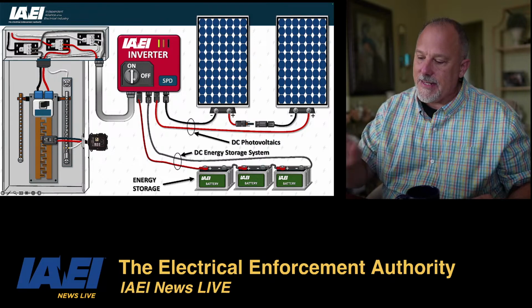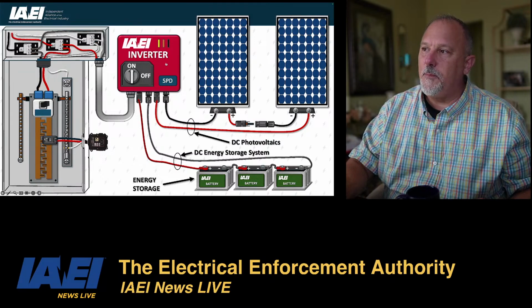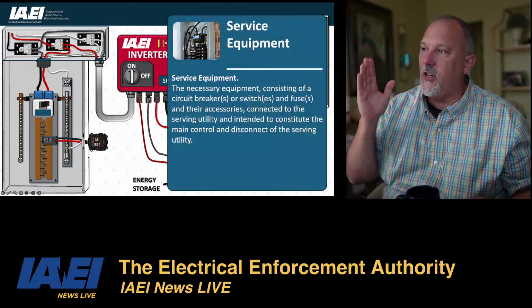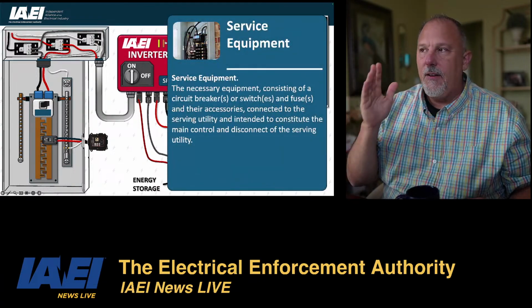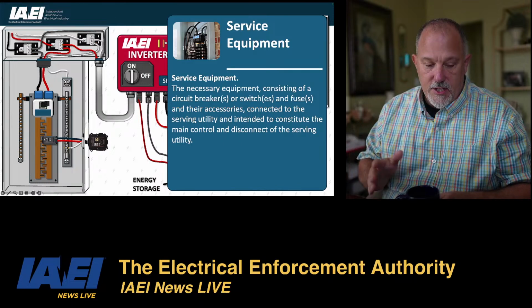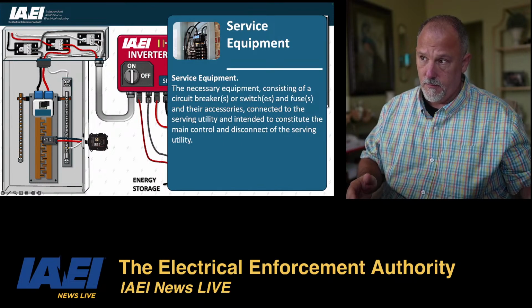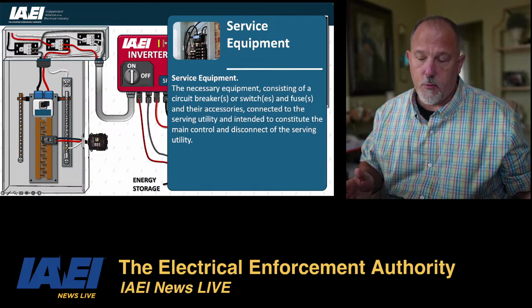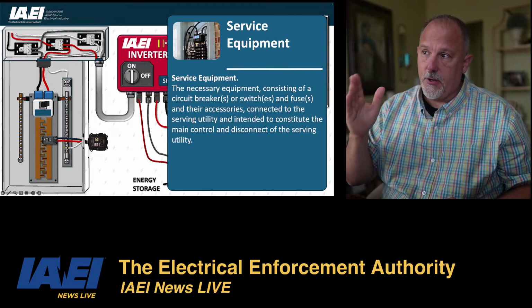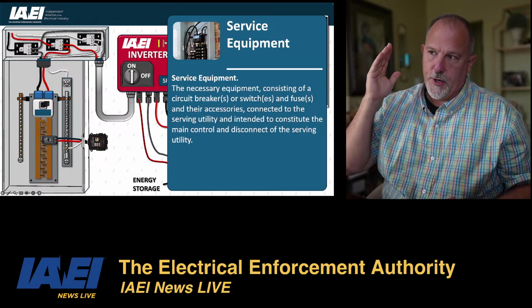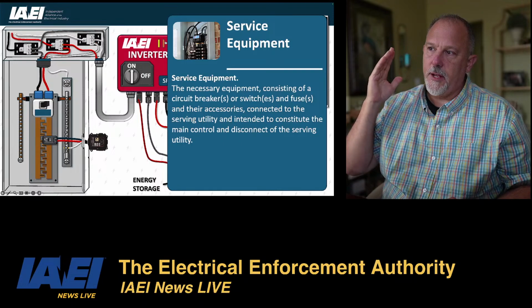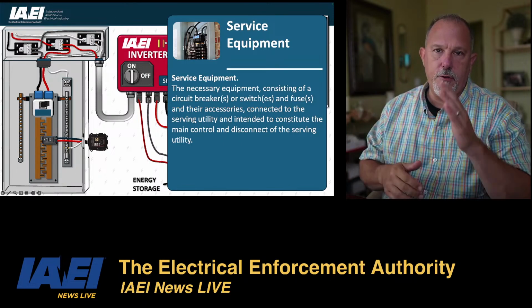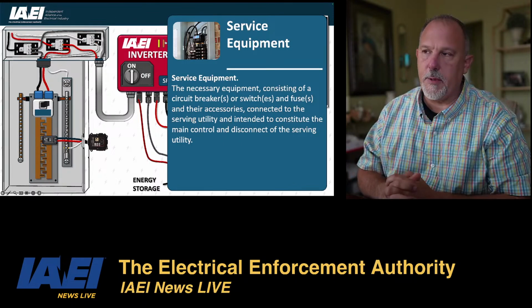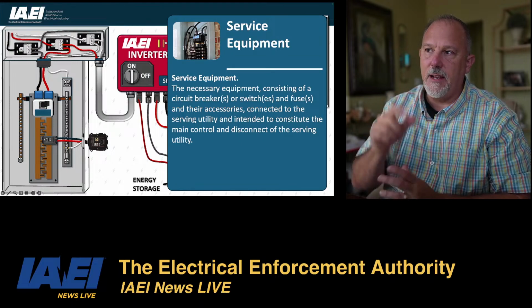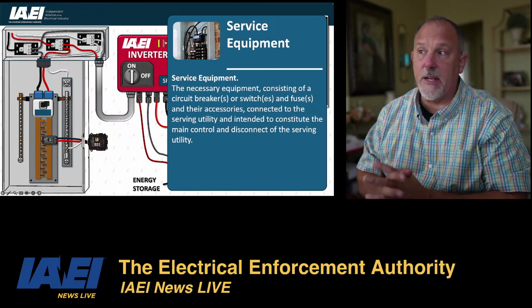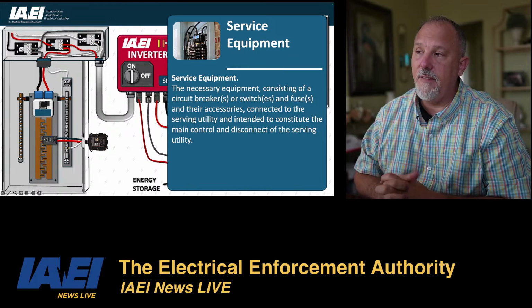Yes, Robert, in this case, the inverter has to be rated as service equipment. So it has to be listed, it can be suitable for use as service equipment or suitable only for use as service equipment. Either way, that is where you're going to do your bonding, and you're going to bring your grounding electrode conductor to this equipment. You're going to have your bonding of your neutral and your ground bar, just like you do on the service panel board. You're going to have line side barriers on the service disconnecting means, because that's a service disconnect. You'll have to have the line side barriers.